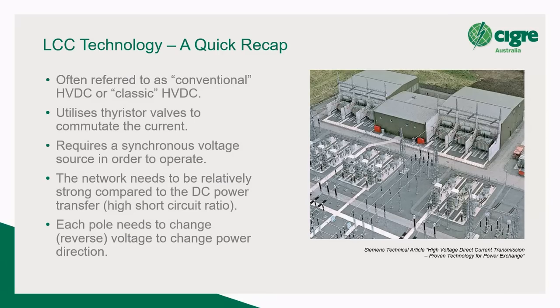So just a quick recap on LCC, referred to as conventional, uses thyristors, requires a synchronous voltage source in order to operate. And because of that fact, it needs a relatively strong network to operate. Okay, the LCC requires a synchronous voltage to commutate, i.e. to allow the current to transfer from one valve to another. So a major disturbance in the AC voltage, whether it's a disturbance in the phase angle or the magnitude, can cause what we call a commutation failure. Now, commutation failures can happen, and a lot of converters can ride through them, but if they're severe and significant enough, they can lead to a tripping of the link. Now, commutation failure is basically when two valves remain on.